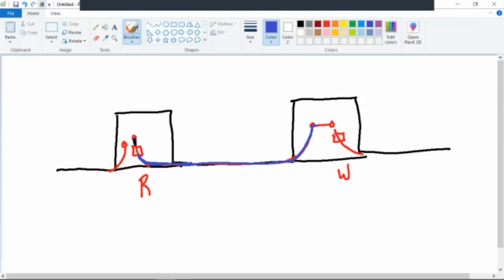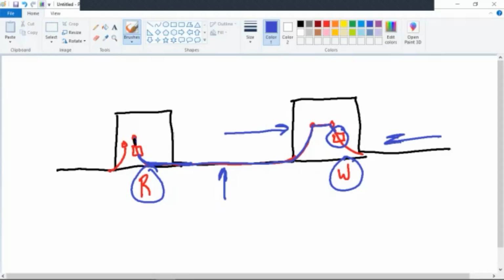Through the transformer? Through the transformer to where? The indicator. The next fault indicator. So remember this, guys, it's not only monitoring the cable, it's monitoring the transformer too. And in some rare cases, I only saw a few of it, lineman came down and they've got a red and a white indicator, and their assumption was, I've got a bad span of cable in here. They isolated it and tried to re-energize from the opposite side. We'll talk about loop re-energization later on. And the transformer was actually bad, so they blew another fuse on this side over here.